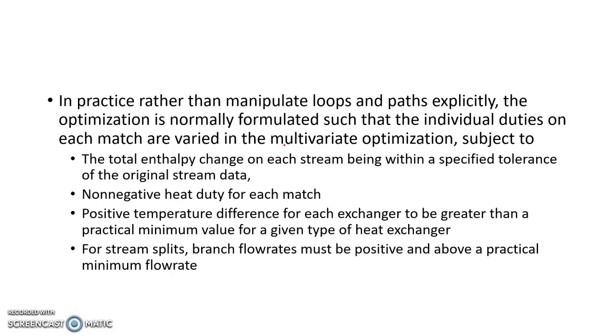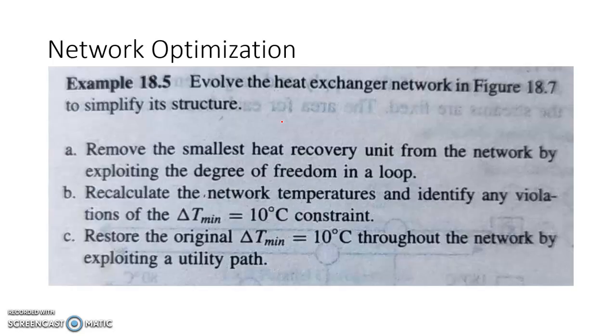The constraints in the optimization are: the total enthalpy change on each stream must be within a specified tolerance of the original stream data; no negative heat duty for any match; a positive temperature difference for each exchanger greater than a practical minimum; and for stream splits, branch flow rates must be positive and above a practical minimum.